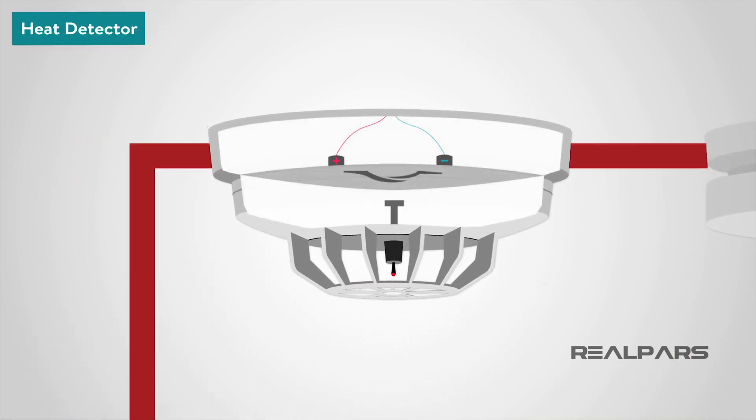Commonly, heat detectors work in a similar way to an electrical fuse. The detectors contain a eutectic alloy, which is heat sensitive. When a certain temperature is reached, the alloy turns from a solid to a liquid, which in turn triggers the alarm.